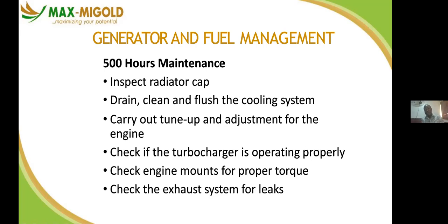Know what a turbocharger is. If the turbocharger is faulty on your generator, the performance of the generator will reduce, because the turbocharger helps to bring in fresh air and expel hot air from the engine. When fresh air is brought into the engine, we give it additional power for performance. Ensure that the turbocharger is in good condition. Check engine mount for proper torque. Check the exhaust system for leaks. If your exhaust system is leaking, it reduces the power of your generator. Ensure that the heat is properly taken out of your generator.